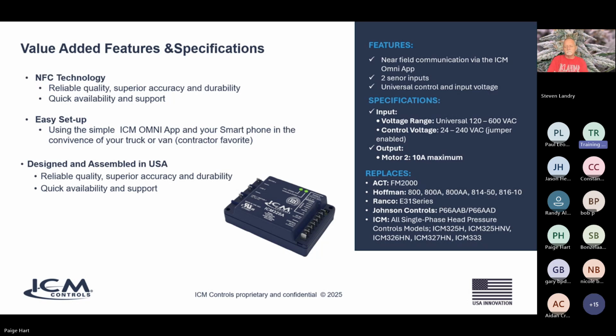So it's a way to program the ICM and set it up without the use of the internet or any Wi-Fi. So there's no Wi-Fi. If you don't have a Wi-Fi network available, you're out in the boonies somewhere, not a problem. Near field communication doesn't require that. It also makes it convenient for people that want to set the control up prior to going up on a windy, cold roof. They can set the control up right in their truck, in the warmth of their truck. They can program several controls if they have more than one control to install, and near field communication will make that possible.